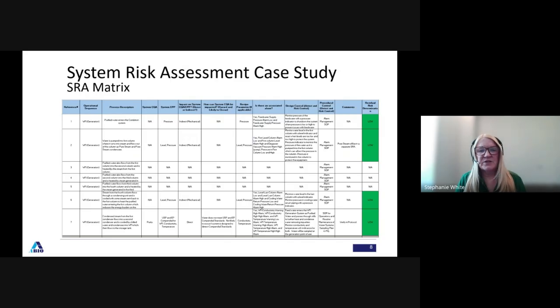However, we determined that it does matter that the flow rates and the pressures that come in, from a mechanical standpoint. And so we deemed that a system CPP could potentially be pressure, even though it is not directly affected by a CQA. And so the next column header says the impact on system CQA CPP, is it direct or indirect? Well, we picked indirect, and the reason being is because the feed water coming in mechanically depends on the pressure or flow rate coming in, but it doesn't have any quality attribute that it impacts.